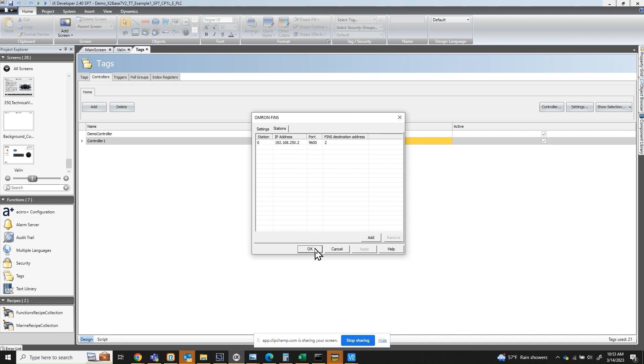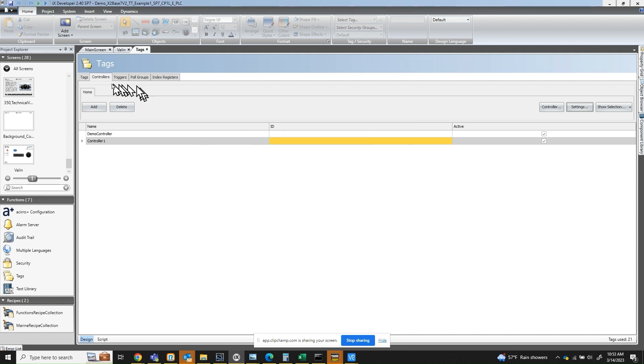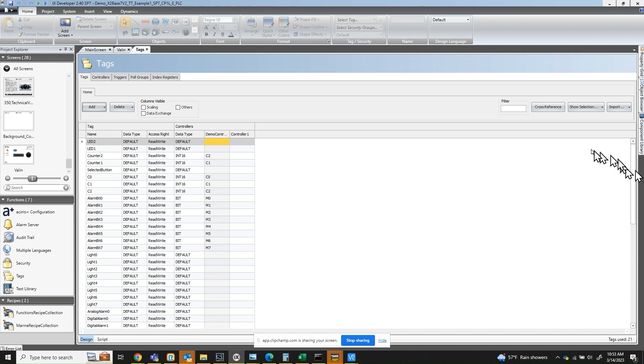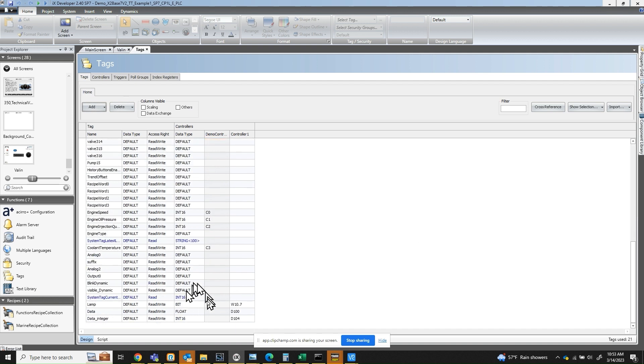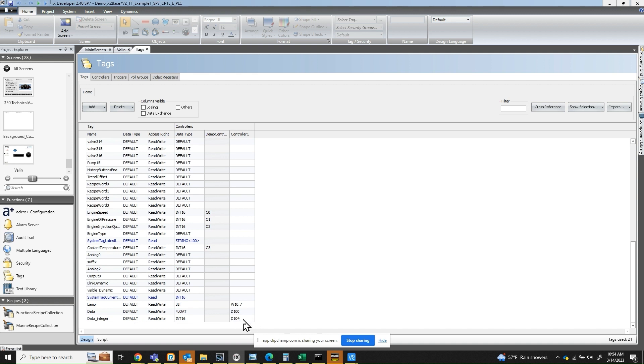So that's the basic setting you need to set up. Then you click OK and go to the Tags tab. This is where you will define all the tags. Right now I have the LAMP that I will be using on my page as well as the switch. The address for that is W10.7. I also have a real data numeric entry using datamemory100, and another numeric register called data_integer using datamemory104. That same tag, datamemory104, is used for the bar graph as well as the dial indicator.